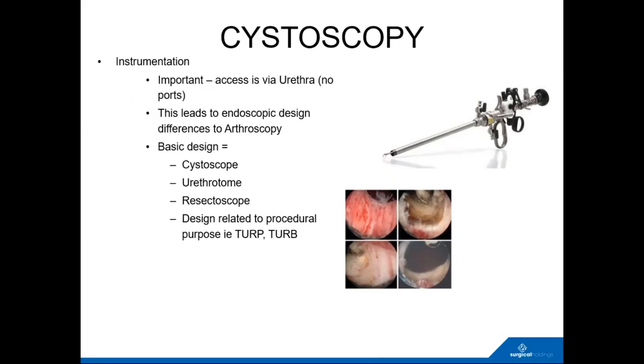I mentioned TUR in cystoscopy. This is an example of a resectoscope. It has a loop at the tip, which will be moved back and forwards using what's known as a working element. The basic design problem with this in comparison to arthroscopy is that you are just using the urethra, so you effectively only have one port. So everything has to be designed to be used in that one dimension.